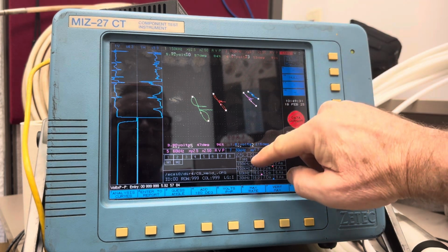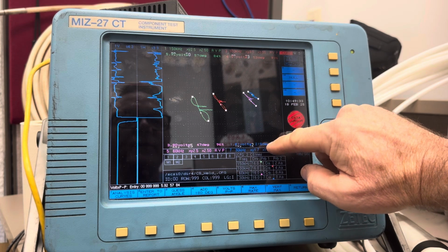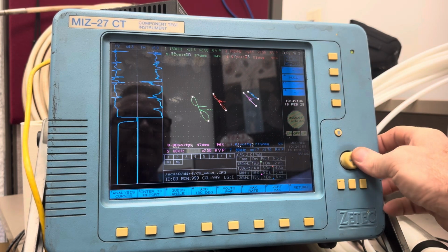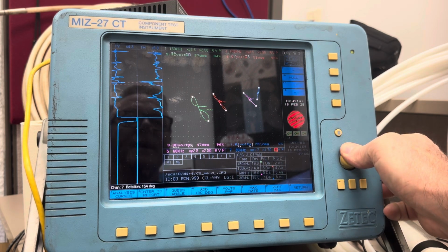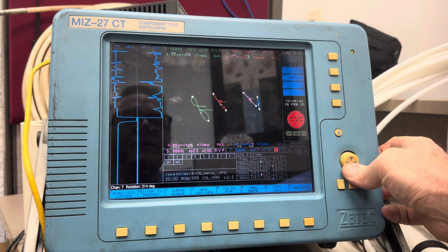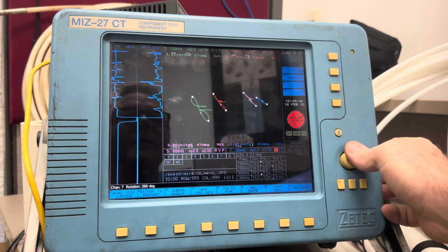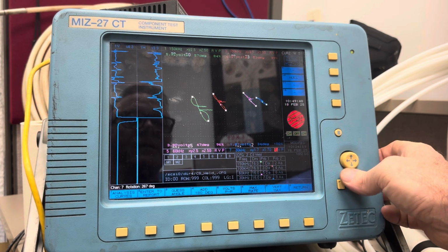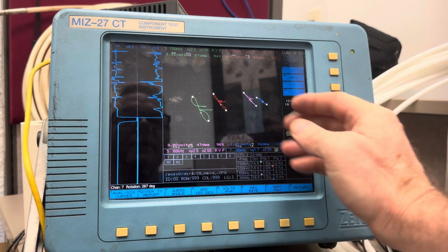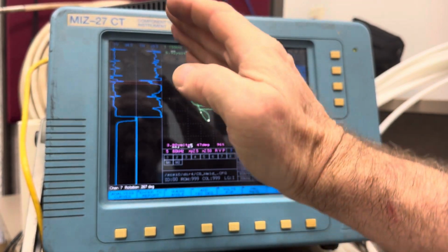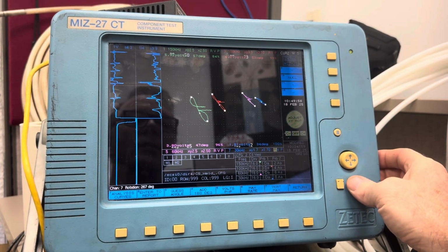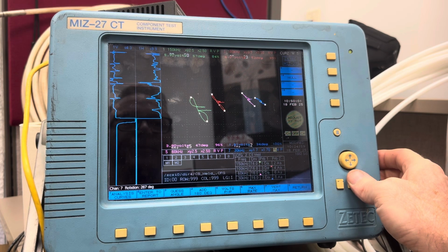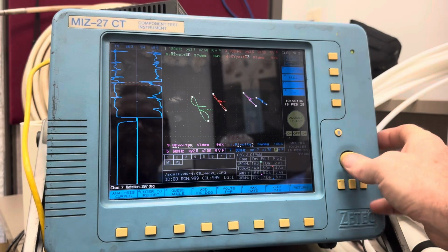And if you go to the blue, that's the lowest frequency, 30 kilohertz. Now you're down to 215, which only means that when I calibrated that particular channel, I wasn't paying attention, and I got it upside down. And since I know this phase is going to be less than 60 kilohertz, it's probably going to be somewhere in there. So 57, 53, 47, 34. That's how an OD flaw rotates with decreasing test frequency.